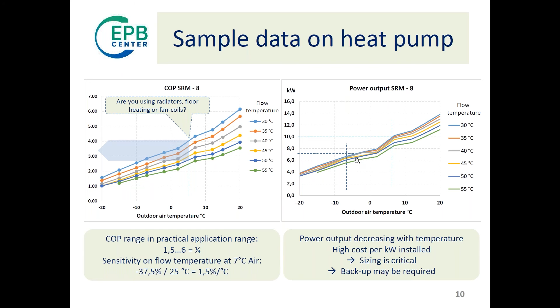If you buy a heat pump, typically the output power is declared at 7 degrees, but you need to go down to -7, -8, or whatever your climate. In any case, when you need the most power, you get the least. So you must be careful about design. No problem, just take it into account. Just to show you that this is quite sensitive.